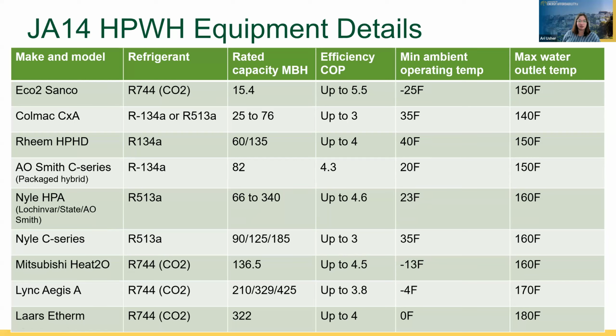So we talked a little bit about some of the different design considerations, but what are the things about the equipment that play into this? I want to just mention the rated capacity. There's a variety of different sizes available. Usually for multifamily, we're not going to see the largest that's needed. That's maybe more for a commercial application, or maybe for a really large building. And then the efficiency, we've got some really great efficiencies, anywhere from 3 all the way up to almost 6 COP. The ambient operating temperature, some of these systems work really well even down to negative 25 degrees Fahrenheit. In California, you may not have a climate where you need to go that low. However, they also have the max water outlet temperature going up to 180. So a lot of different options there based on what you need for your project.